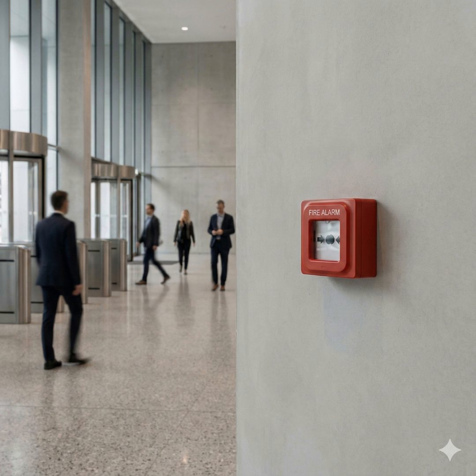Then the final and maybe most complex element of notification is the voice systems, the Emergency Voice Alarm Communication Systems, or EVACS. This goes beyond simple tones to deliver actual instructions. And the scientific standard that governs the clarity of those messages is the Speech Transmission Index, or STI. EVACS design requires field testing to ensure a minimum 0.50 STI score for any life safety messaging. The STI score is basically a number that quantifies the quality and clarity of the speech, the intelligibility. So if the score is too low, the message is just garbled. Muffled, garbled, washed out by the room's acoustics.